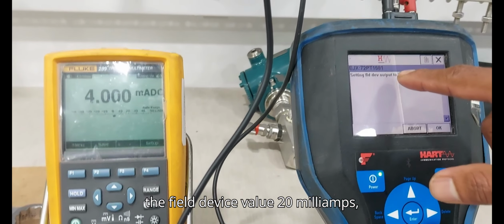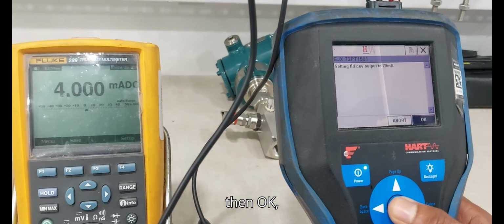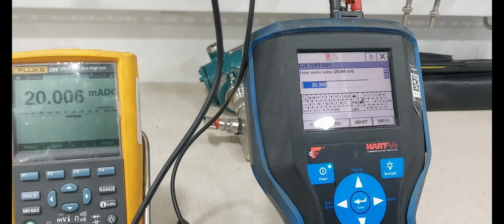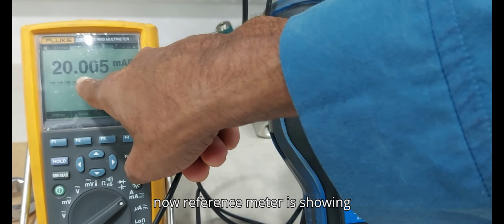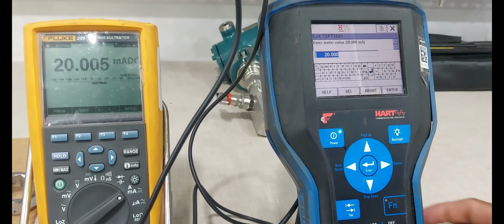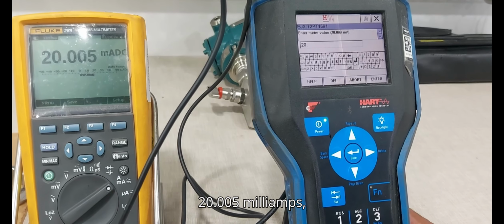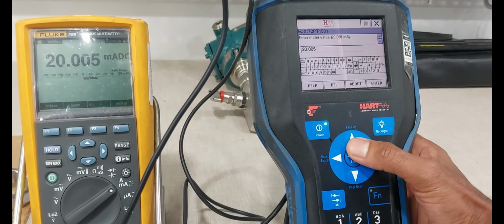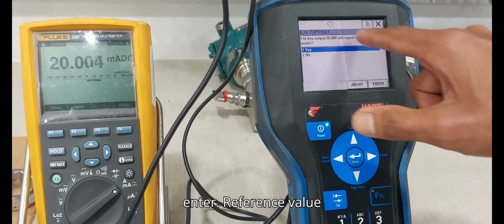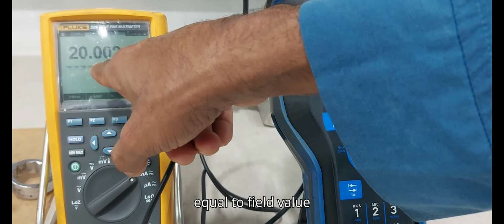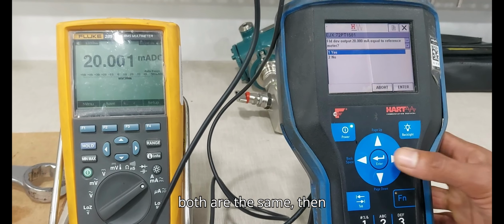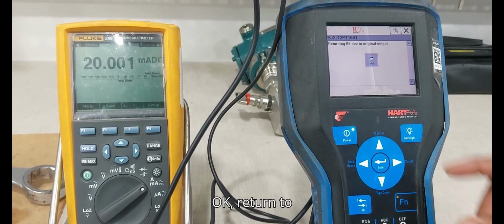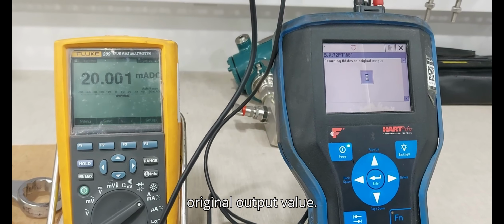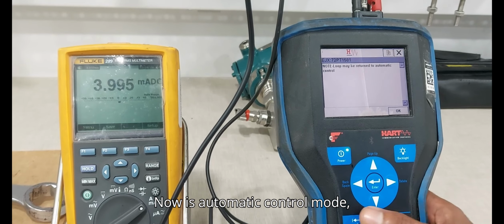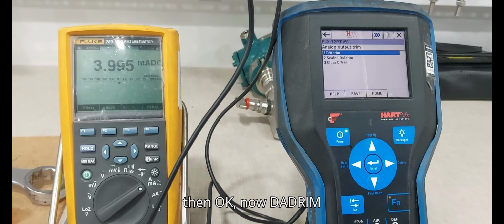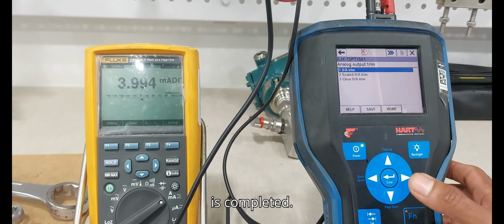Next is setting the field device value 20 milliamps. Then OK. Now the reference meter is showing 20.005 milliamps. We apply the same value, 20.005 milliamps. Enter. Reference value equals field value. Both are the same. Then OK. Return to original output value. Now it is automatic control mode. Then OK. Now DA trim is completed.